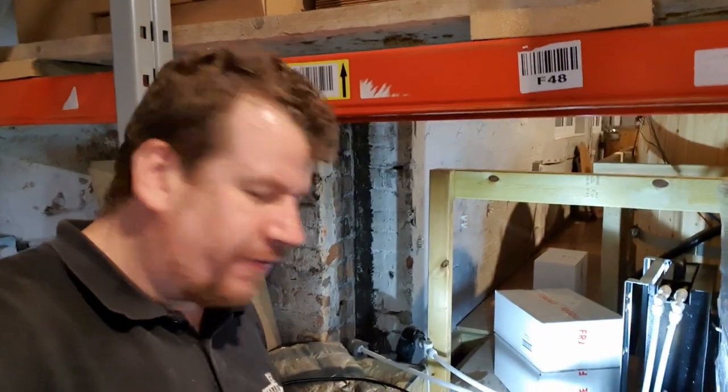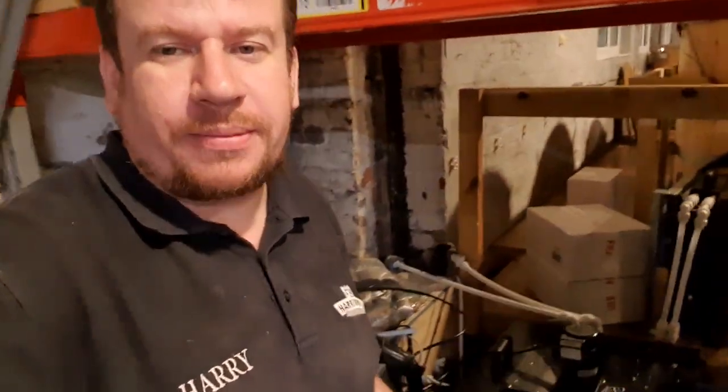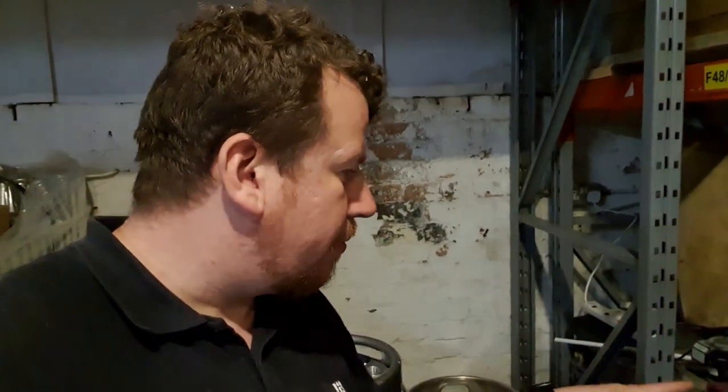I think that's going to conclude today's vlog. I'm quite happy that I've got this working again, but in the morning I am going to relocate all of this equipment and probably pull out the old unit, decommission it, drain down the glycol because I can use that again, and tidy the whole area up. We'll probably put that hydrocarbon cooler in there permanently because I'm not going to need it throughout the winter to run the cold rooms — they are going to be warm rooms as we move into the colder weather. That will give me enough time to order another cooler from Booth Limited. There was a six-week lead time on them, so we've got a good six months before the hot weather comes back — that will keep us going until then.